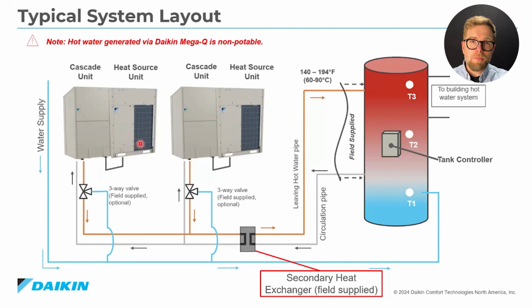Picture two refrigerant loops working in tandem. First, we have the heat source unit outside. It circulates R410A refrigerant, just like a VRV air-to-air heat pump. By absorbing heat from the outdoor air, even when it's super cold, it circulates a stream of high-temperature R410A. This stream then flows into a cascade unit, which is where the magic happens. Inside the cascade unit, that hot R410A transfers its heat to a second refrigerant loop running R134A.